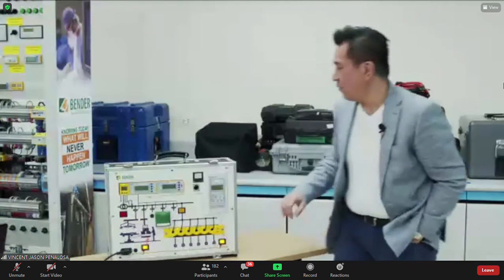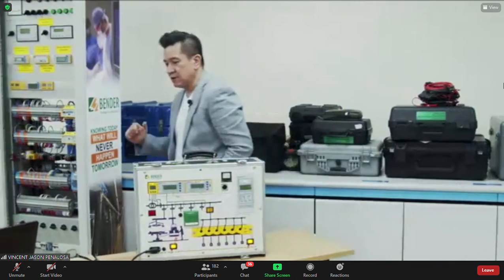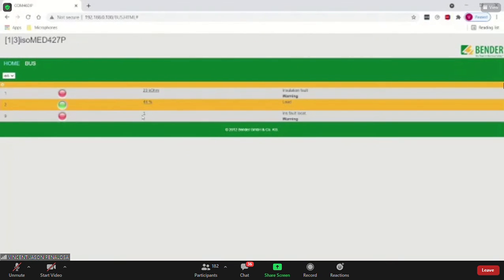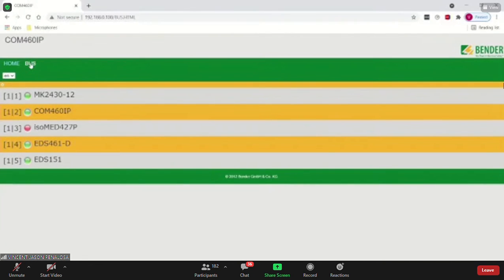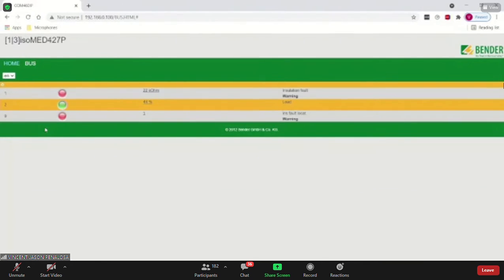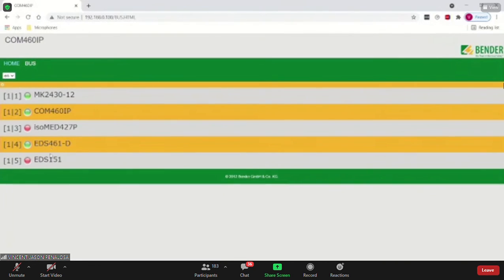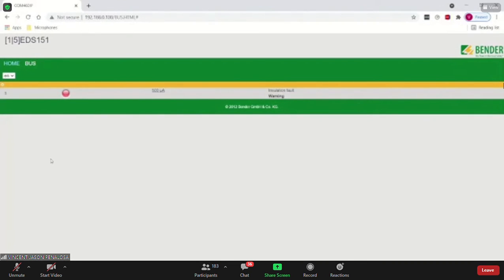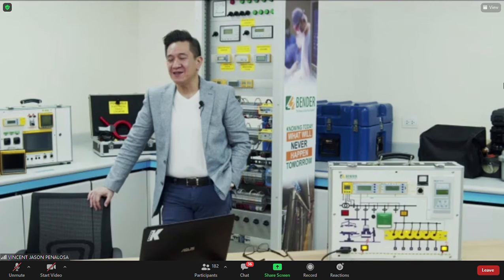There. Now, to make sure, I'm going to look into my system. By the way, guys, I apologize. My software right here is the old one. All right. So the ISOMED tells me that, yep, you have an insulation fault. All I have to do now is actually try to find it. So here, the ISOMED tells me that it is on channel 3, and I have a 500 microamp fault. It's a small fault. That's how sensitive it is.